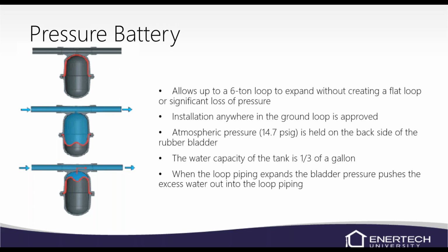You can basically install it anywhere in the ground loop, and atmospheric pressure, or roughly 14.7 PSI, is held on the back side of the bladder, and it's got about 1/3 of a gallon of water. Basically, when the loop piping expands, the bladder pressure pushes the excess water into the loop piping. So it's just kind of like an expansion tank.